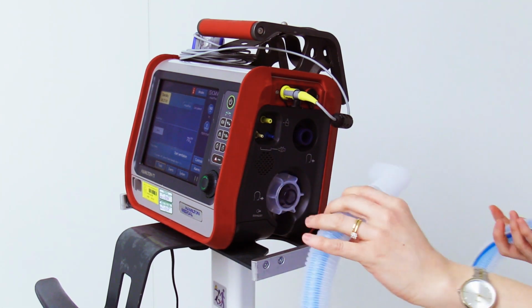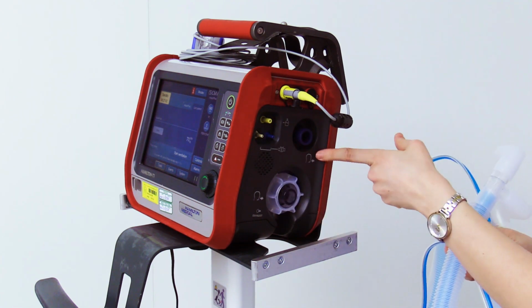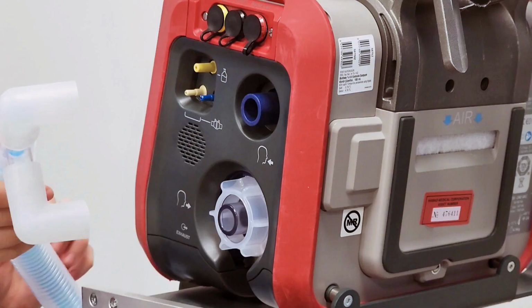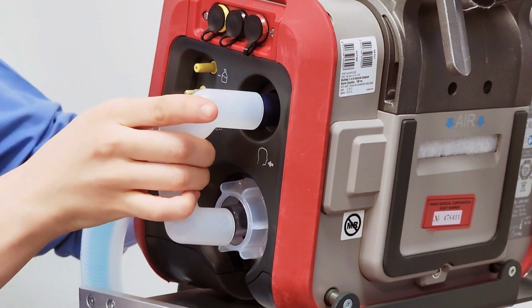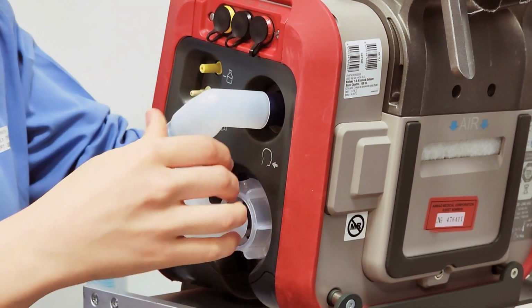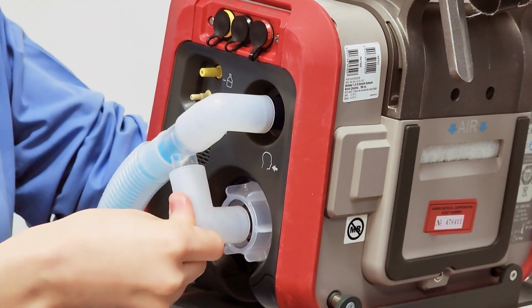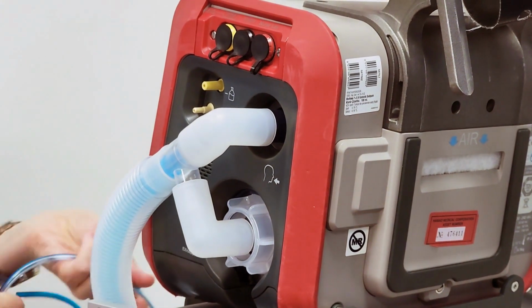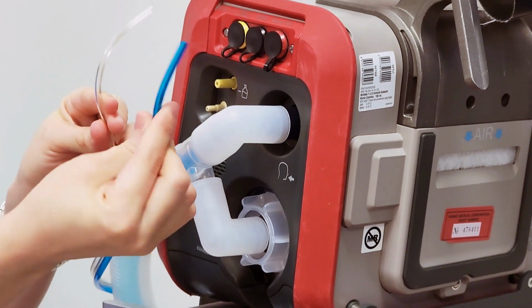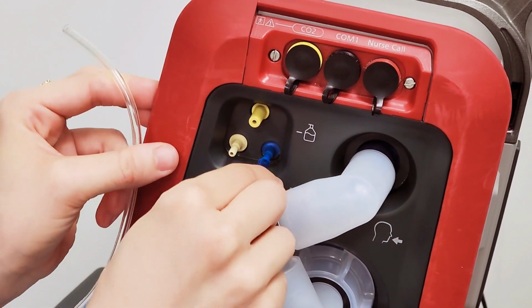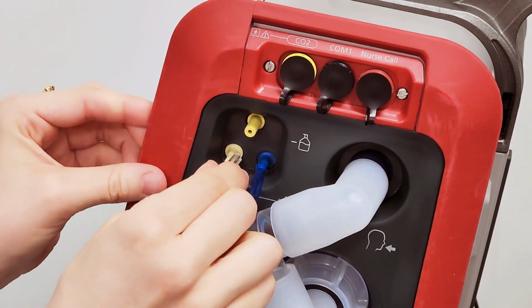Now you have to attach the circuit to the inspiratory port and the expiratory port. Properly secure both the exhalation and inhalation limbs of the breathing circuit, and then connect the flow sensor tubing. Connect the blue tubing to the blue port, and the transparent tubing to the white port.